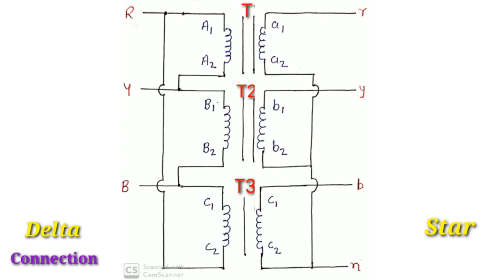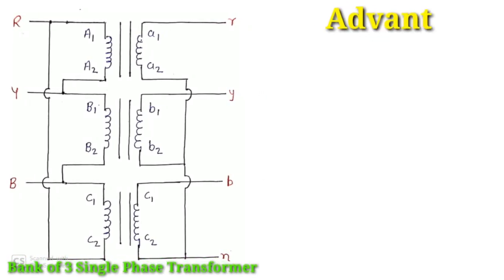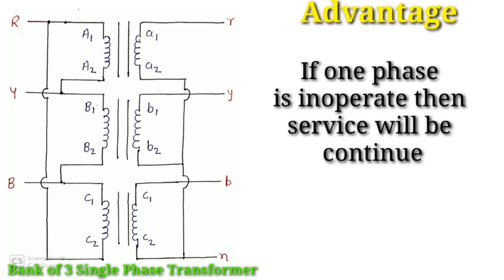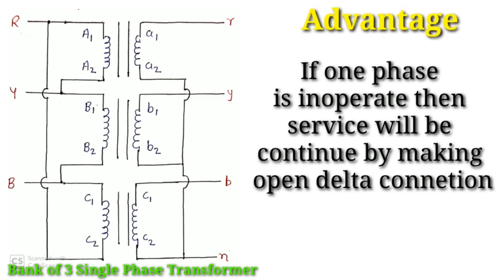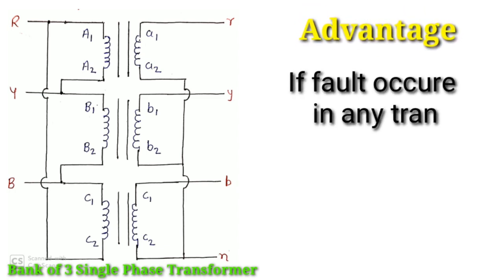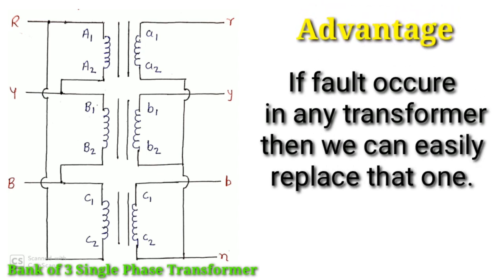With this connection, a bank is formed which is connected in delta-star. After forming this bank, the main advantage is that if one phase becomes inoperable or stops working, we can continue service by making an open delta connection. If a fault occurs in any one transformer, we can remove and repair or replace that transformer.